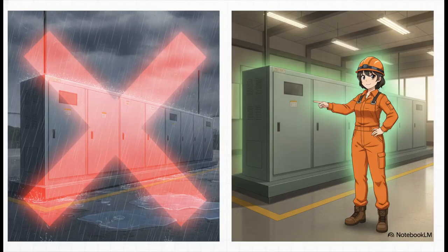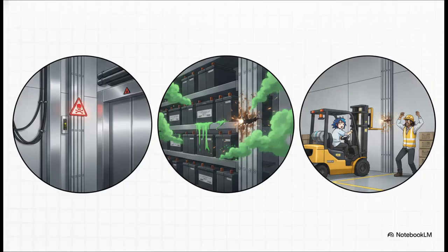You absolutely cannot. Rule 12-2000 tells us that busways and splitters are generally meant for exposed, indoor work. You can't put them outdoors or in wet or damp locations unless the gear is specifically stamped and marked by the manufacturer for those exact environments. If you don't see a NEMA 3R or an equivalent weatherproof rating stamped right there on the metal, keep it inside, for sure.